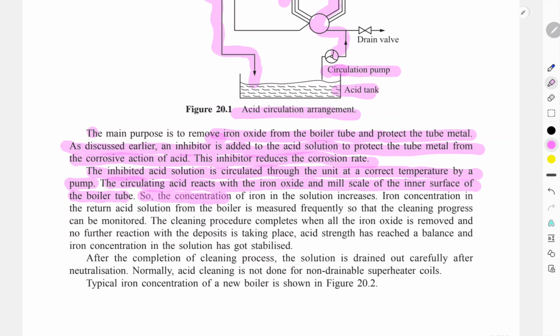So the concentration of iron in the solution increases. The iron concentration in the return acid solution from the boiler is measured frequently so that the cleaning progress can be monitored. When the cleaning procedure is completed, all the iron oxide is removed and no further reaction takes place. The acid strength has reached a steady level and the iron concentration in the solution has stabilized. After completion of the cleaning process, the solution is drained out carefully. Normal acid cleaning is not done on non-drainable superheater coils. Typical iron concentration in a new boiler is shown in the figure.